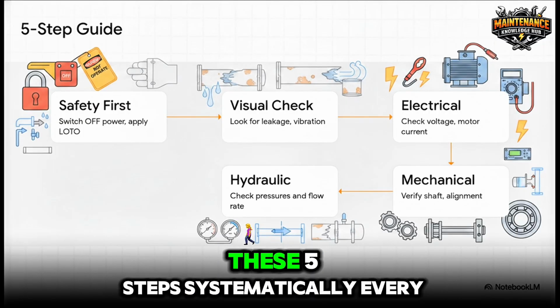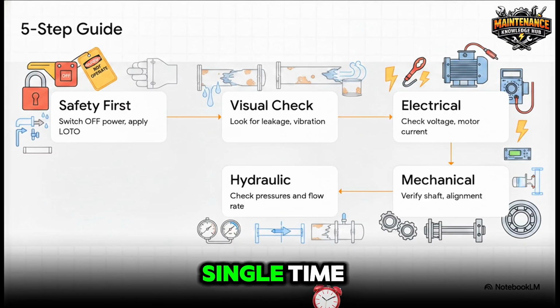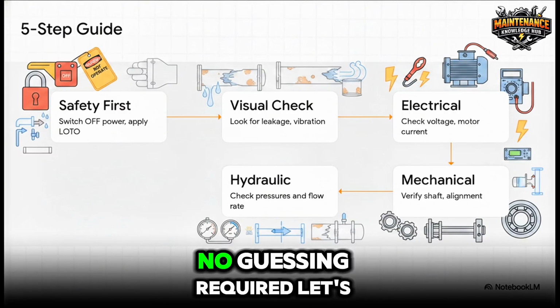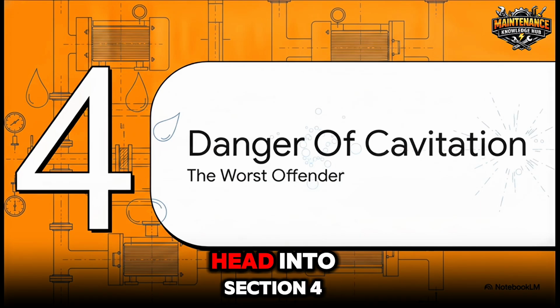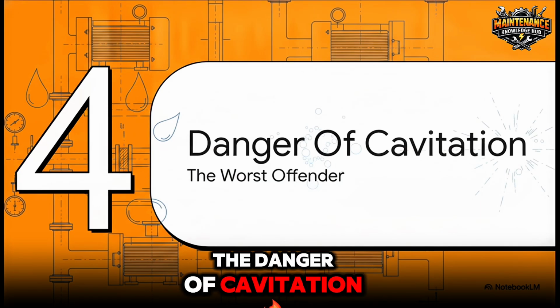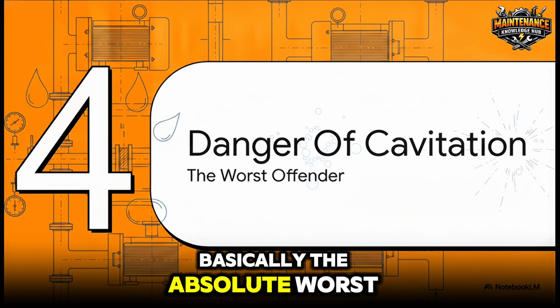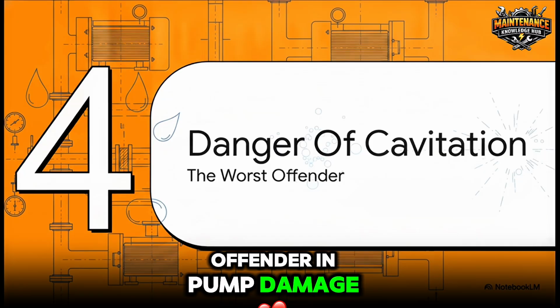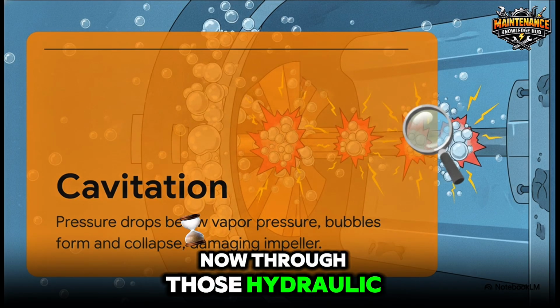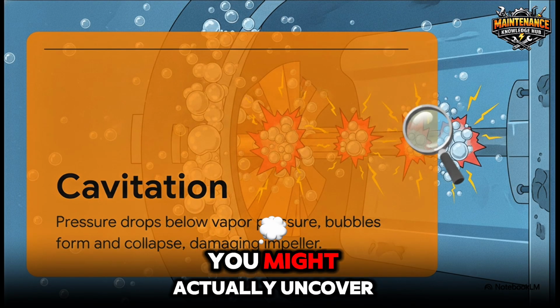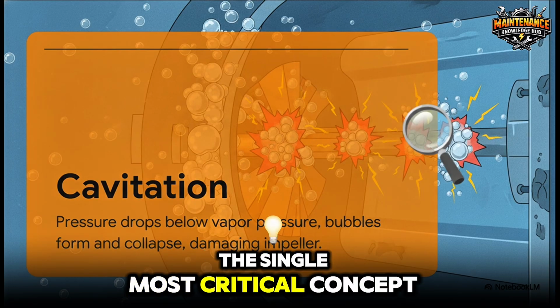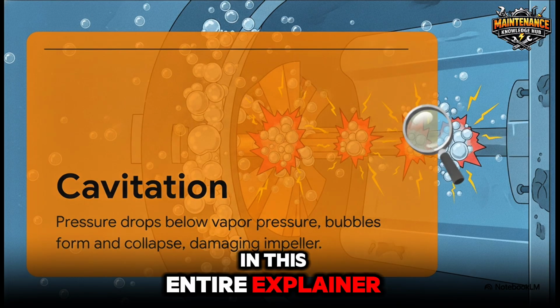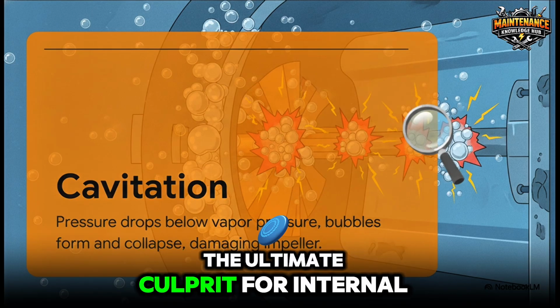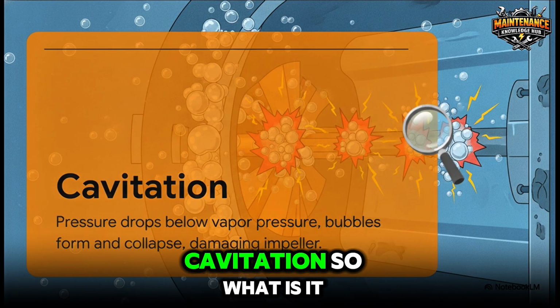Honestly, if you follow these 5 steps systematically every single time, you are going to isolate the problem. No guessing required. Let's head into section 4, the danger of cavitation, basically the absolute worst offender in pump damage. Now, through those hydraulic checks we just talked about, you might actually uncover the single most critical concept in this entire explainer. We are looking at the ultimate culprit for internal pump damage, cavitation.